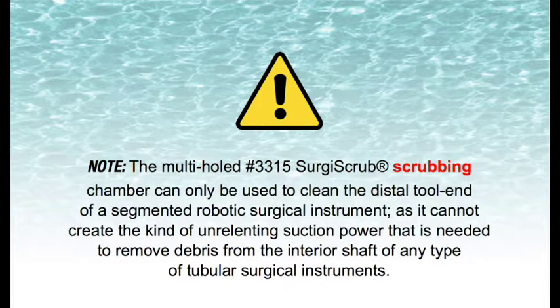Please note: the multi-hole No. 3315 SurgiScrub scrubbing chamber can only be used to clean the distal tool end of a segmented robotic surgical instrument, as it cannot create the kind of unrelenting suction power that is needed to remove debris from the interior shaft of any type of tubular surgical instrument.